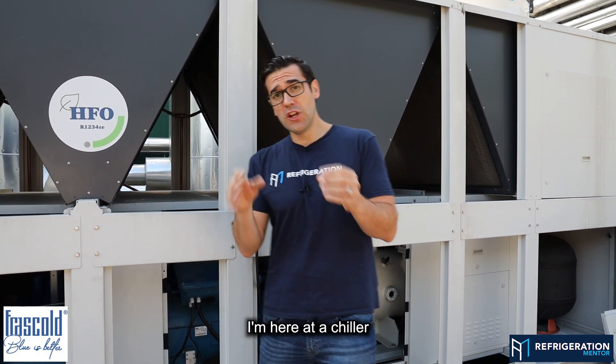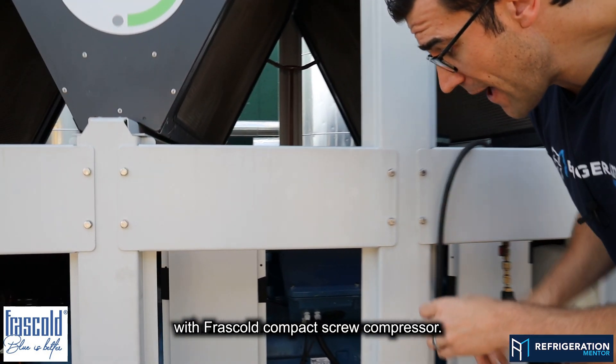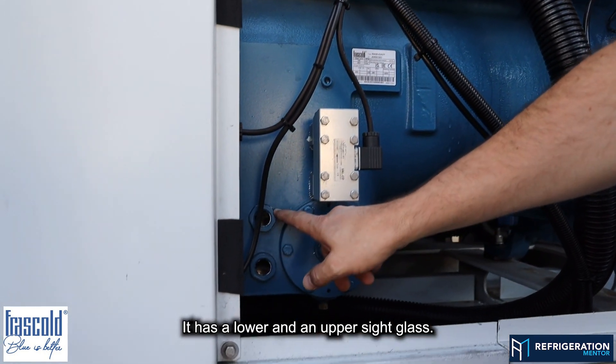I'm here at a chiller with a Frascold compact screw compressor, and here is the oil sight glass. This one has two sight glasses — a lower and an upper sight glass.